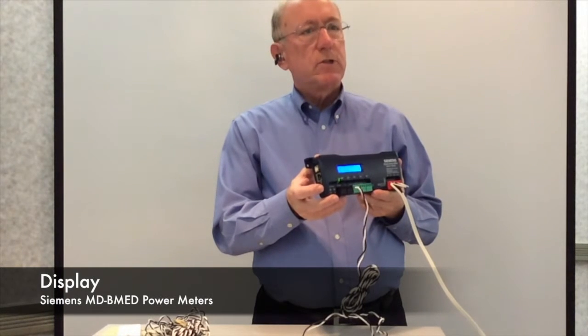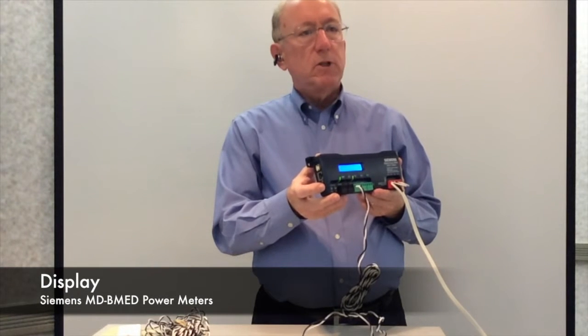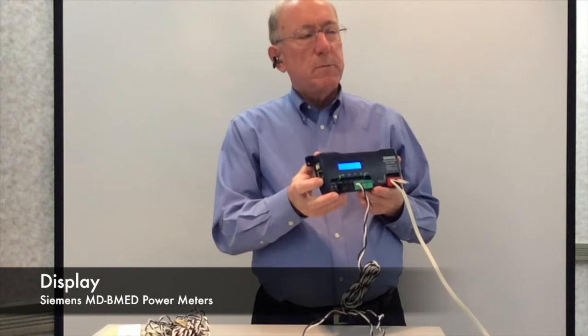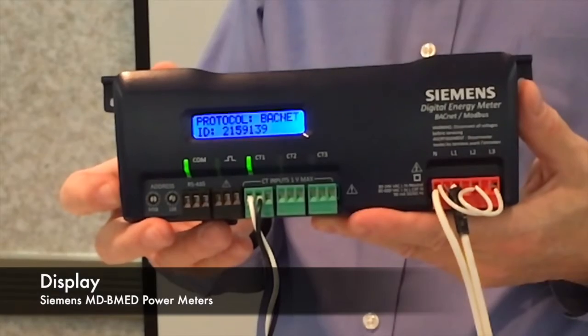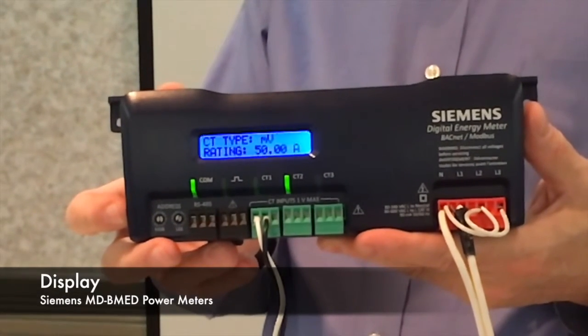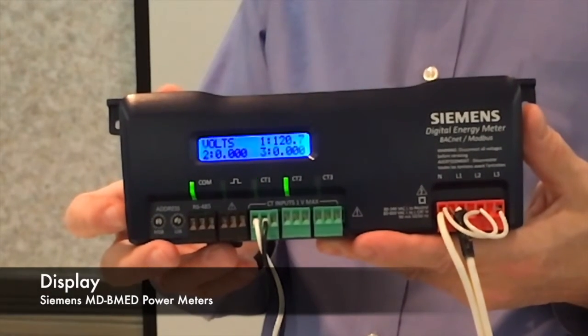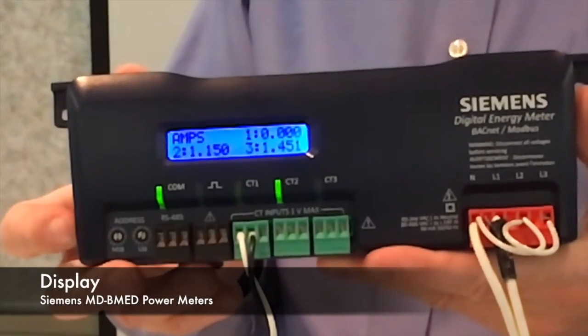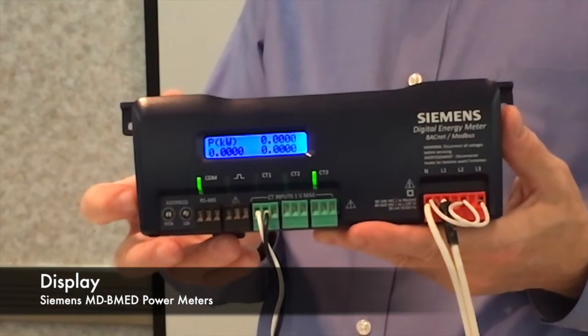The Siemens MD power meters come in two flavors. The first is the basic unit with no display. It's a very functional unit that does everything you'll need for power and energy measurement. The second, premium unit offers the additional Ethernet, but more specifically, a rotating display that has 2 lines by 16 characters, is backlit, and provides the key operational data that you would want to verify during setup before your communication is connected to your BMS system.